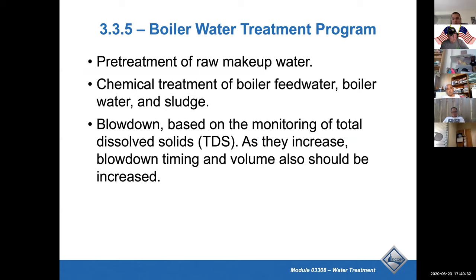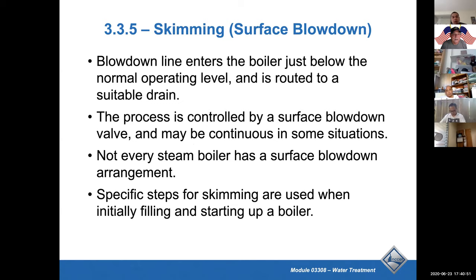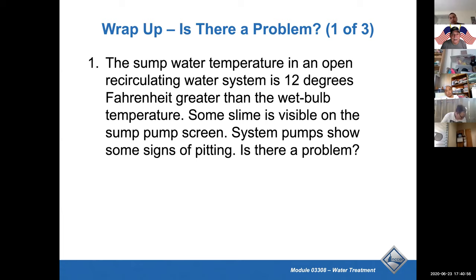Basically, they treat the makeup water that goes into a boiler, and they do blowdowns to control total dissolved solids. They usually have an automatic control on that. Okay, surface blowdown skimming. Let's skip that.